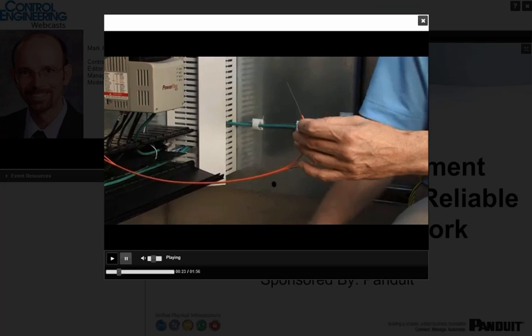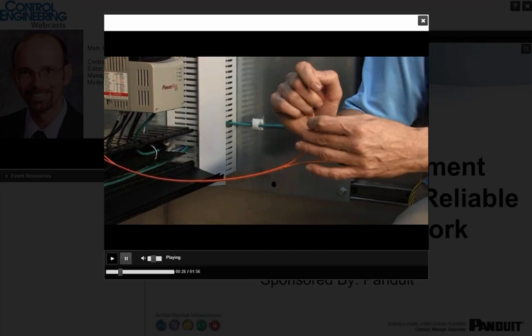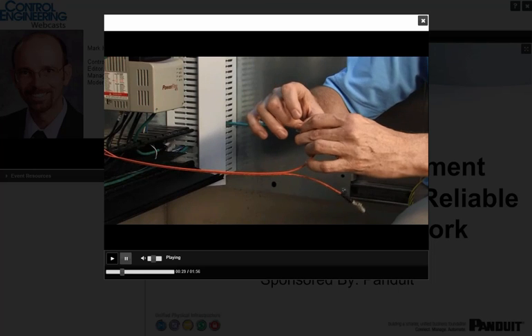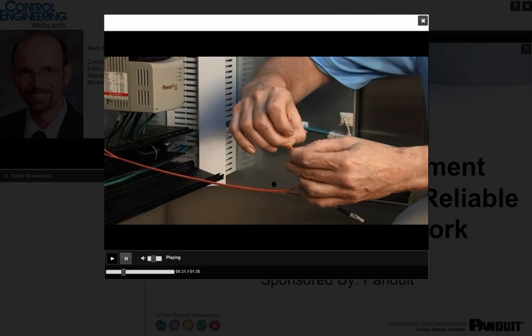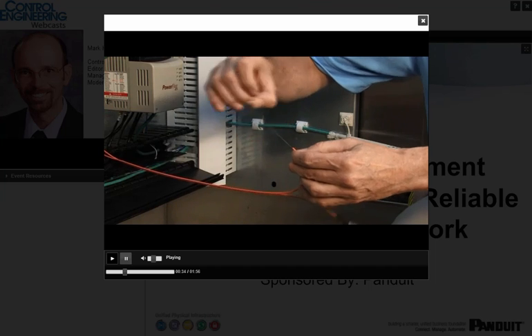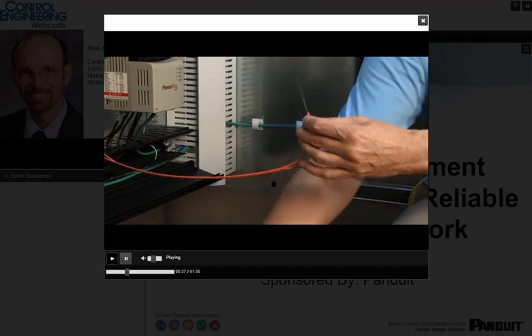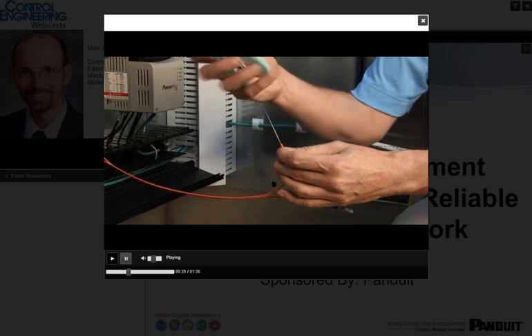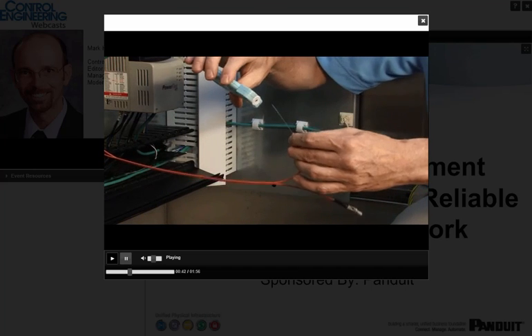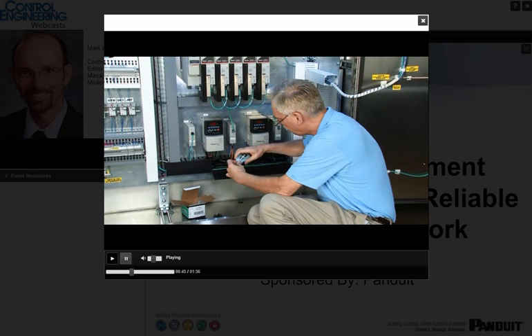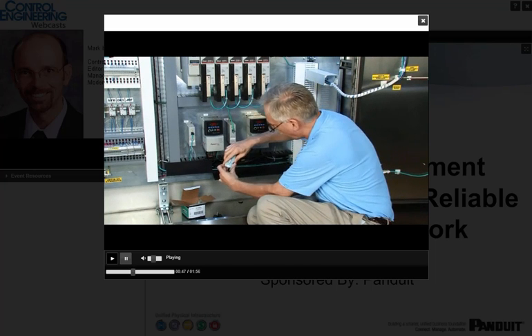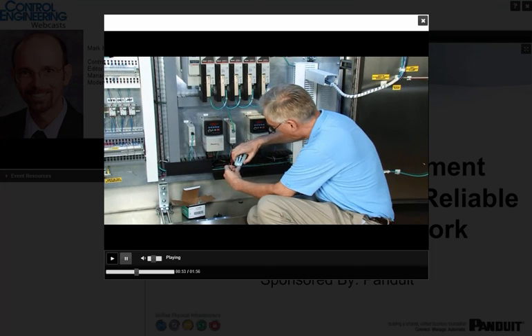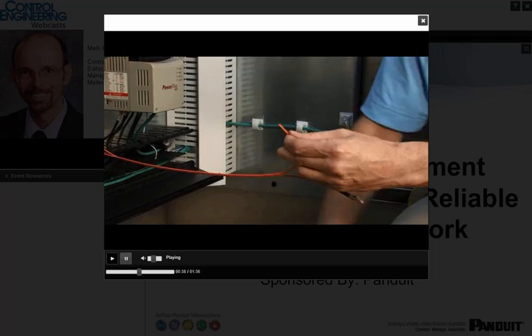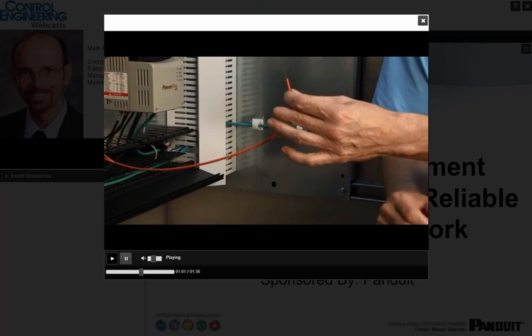So the next step is I want to remove the primary coating off of the cable. To do that, I'm going to take a little bit of a finger stretch with my fingers just to delaminate the primary coating from the PCF fiber. I'm taking my microstrip tool to take off the primary coating and inserting the fiber into the microstrip. I'm going to use typically two passes. Now I have taken off the primary coating.